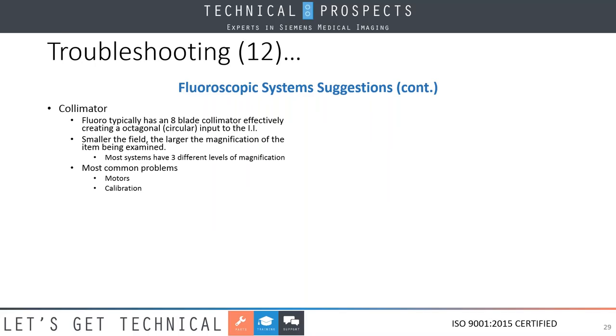All right. Our collimator, especially in fluoro, is typically 8 blades. All right. Creating an octagonal or circular input to the II. You have 3 different levels of magnification. All right. Basically, what we do is we reduce the input to the II and then create that smaller input up at the output. And that's how we get magnification. The problem with our collimator here typically is motors and calibration. All right. With an emphasis on the calibration.